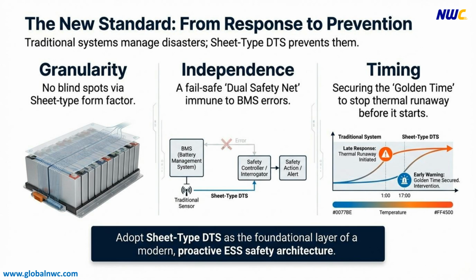NWC's sheet-type DTS proactively prevents ESS fires through precision monitoring with no blind spots and an independent dual-layer safety architecture that remains operational even if the BMS fails. In particular, its early warning capability, securing the critical golden time before thermal runaway occurs, represents the core of a next-generation safety architecture, going far beyond traditional reactive approaches. With its three key values, precision, independence, and timing, sheet-type DTS sets a new benchmark for ESS safety standards.